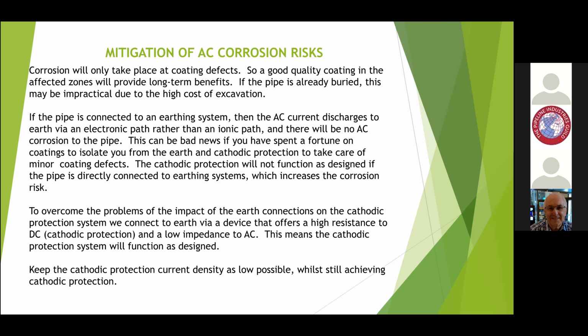And the way to do that is to make a direct connection between the pipe and the earth. If you earth the pipe, the current will flow through the earth and it won't corrode your pipe. It will flow through the cable into the electrode you've got in the earth, and it will return to where it wants to go. That's great, but it means that your cathodic protection won't work, because your cathodic protection is there to provide DC current onto the defect to stop it corroding, which we covered in one of the earlier presentations, and the PIG has other presentations on cathodic protection, which are referenced at the end of this. So now you've got the dilemma where you've got the AC on the pipe, which you don't want, but the best way to get it off is to impact on the cathodic protection, which will then allow the pipe to corrode because there's no cathodic protection.